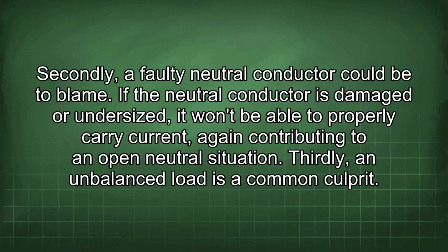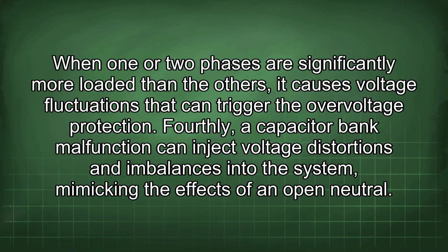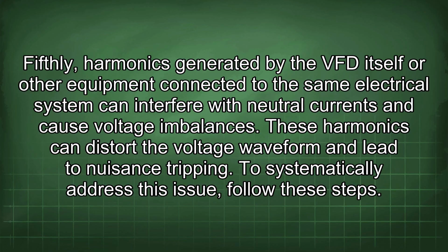open neutral situation. Thirdly, an unbalanced load is a common culprit. When one or two phases are significantly more loaded than the others, it causes voltage fluctuations that can trigger the overvoltage protection. Fourthly, a capacitor bank malfunction can inject voltage distortions and imbalances into the system, mimicking the effects of an open neutral. Fifthly, harmonics generated by the VFD itself or other equipment connected to the same electrical system can interfere with neutral currents and cause voltage imbalances. These harmonics can distort the voltage waveform and lead to nuisance tripping.